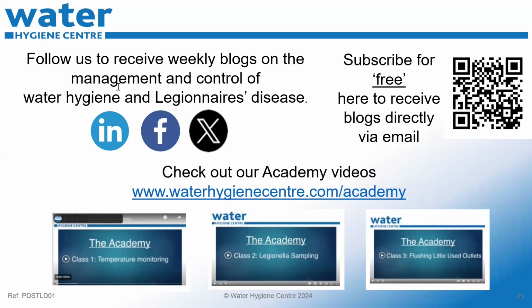And my suggestion would be that we go to a filtration system and a UV disinfection system, which again is quite straightforward and just continues to work like your UV disinfection in a pond, for example. As long as the water goes through there and it's removing some of the organics, the suspended solids, it will allow the UV light to go through and hit the organisms rather than the suspended solids within there. So we've got to filter it first and then UV would be my suggestion.